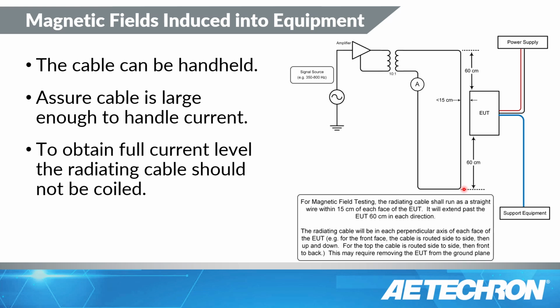You can just handhold that wire and sweep it on all sides, making sure that the distance between the cable that you're using and the unit is less than 15 centimeters. The other thing is that you're going to perform this test in 2 axes on each face. So that means left to right and up and down. So let me take a look at the top here. You're going to do it from top to bottom, and you're going to do it from left to right. So there's 2 axes on each one of these sides. You're going to do the top face, you're going to do the front face, left, back, and right face. Right or left, maybe backwards, depending upon which direction you're looking at this, I suppose.